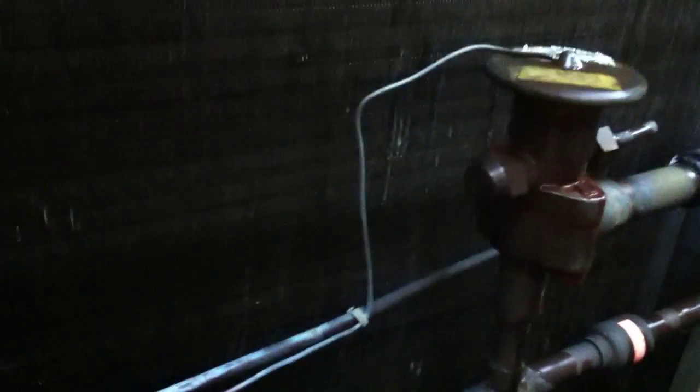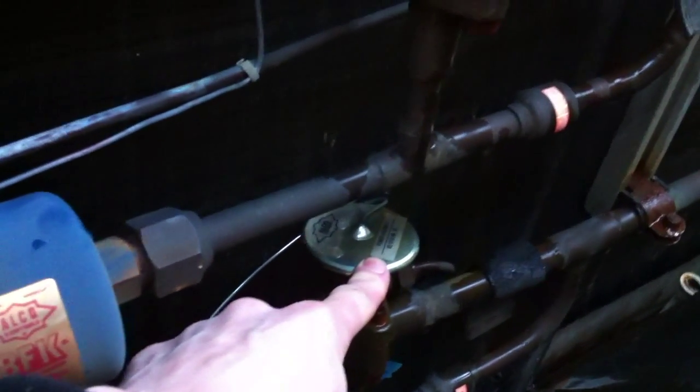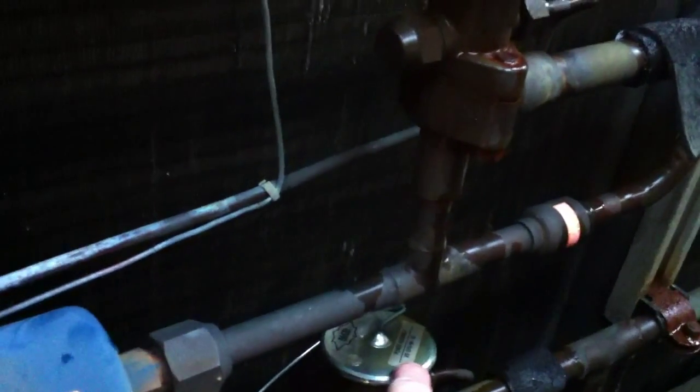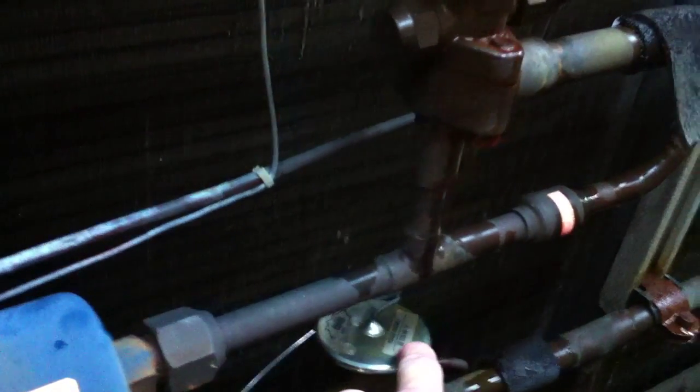I've got the frost melted off the coil, took the power feed off the reversing valve. Although it wanted to be in heating mode, it actually ran in cooling. It's cleared all the ice off. I suspect that valve's gone — probably the power element's gone on it. It's an Alco XB1019HW-1B.